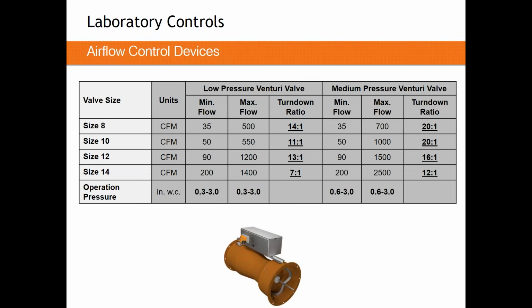Now that brings us to the Venturi valve again here, but we have to read this data differently. I'm going to focus mostly on the right-hand side of the chart here on the medium pressure Venturi valve. Valves, for the record, come in 2 styles, low pressure and medium. The sacrifice you make to go to the low pressure valve is your maximum airflows are lower. So on a size 8 box, instead of going to 700 CFM, it will go up to only 500 CFM. However, it can be operated down to 0.3 inches instead of 0.6. So knowing that, we'll stick to the performance of the medium pressure valve.